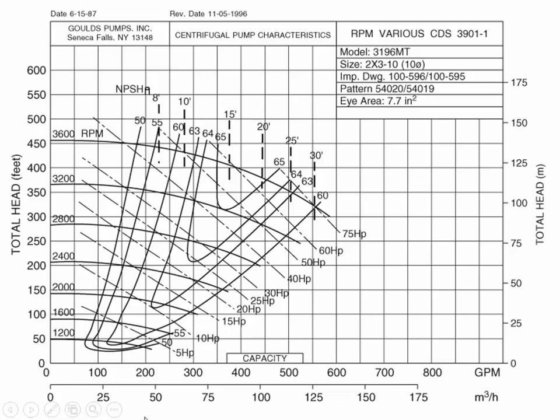And you'll notice that as the flow rate increases down here on the x-axis, as the Q goes up, the head it's able to add decreases. The other thing I want to point out is that these curves here are kind of like contour lines describing the efficiency. If you happen to use this particular pump at these conditions right here, it would be 65% efficient. Or at a lower flow rate, 64% efficient, and so on. But it looks like about the best this pump is going to do is 65% efficient. The last curves on here are NPSH, which means net positive suction head, and we'll get into the interpretation of that in just a minute.